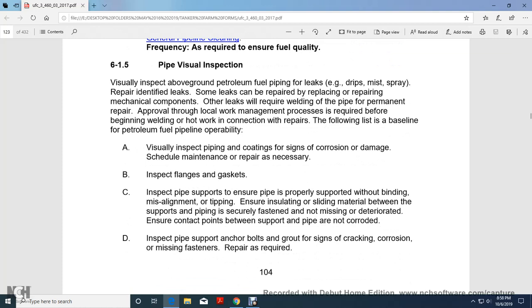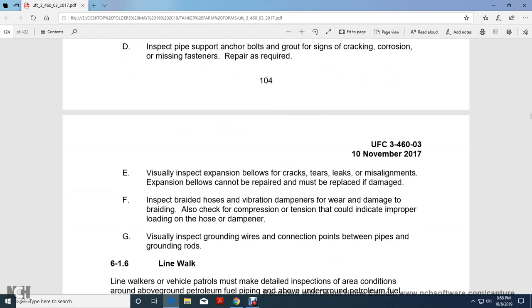Visually inspect the piping and coatings for corrosion and damage. If the schedule allows for repairs as necessary, inspect the flange gaskets. Inspect the pipe to ensure it is properly supported without binding or misalignment. Ensure the isolating sliding material between the support and the piping is securely fastened, not missing or deteriorated, and that the contact points between the support and pipe are not corroded. Inspect the pipe supports and anchor bolts for signs of cracks, corrosion, or missing fasteners; repair as required. Visually inspect the expansion bellows for cracks, tears, leaks, and misalignment. Expansion bellows cannot be repaired and must be replaced if damaged.